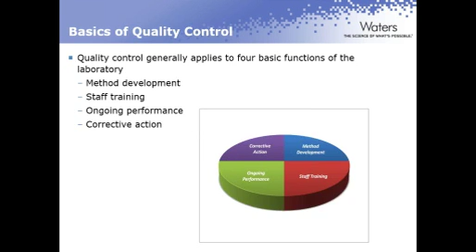So let's talk about the first function, which is method development. There are several areas that need to be addressed in method development. The first is precision. We need to make sure that we have acceptable precision in our method. We'll do that by running a CRM several times in a row to determine the repeatability of a method. So we need to make sure that the method we're using is going to be repeatable enough to meet the uncertainty requirements of our regulatory agency or possibly of our client.